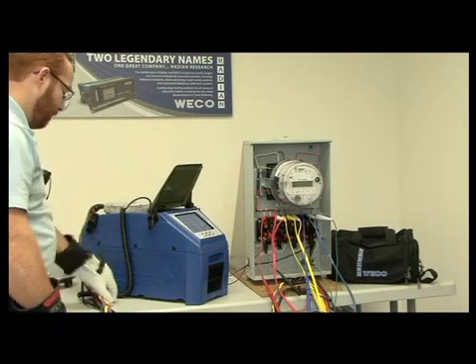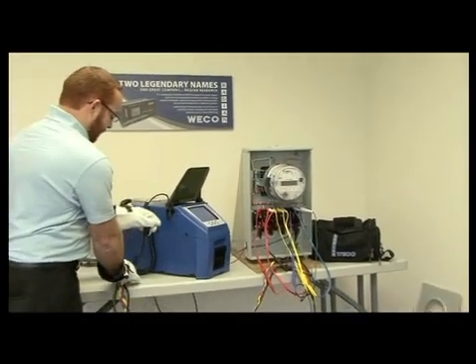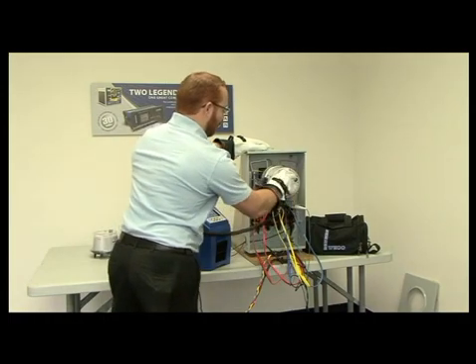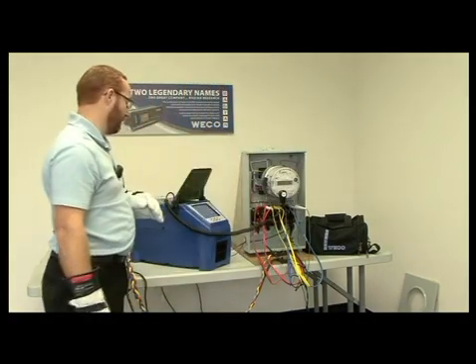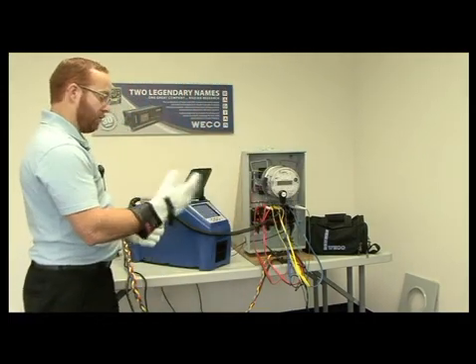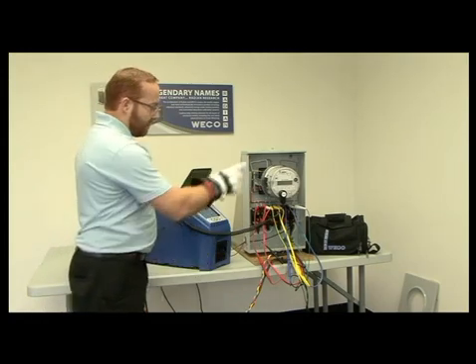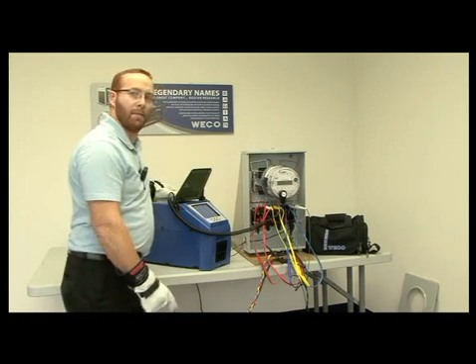Once I have my current and voltage connected and my meter isolated from the CT service, I can install my pulse probe. This is the OptiCom probe that we're using today. And then I can either use my gloves or take my gloves off to operate the equipment, but I'm going to select the meter setup for the test that I'm going to perform today.